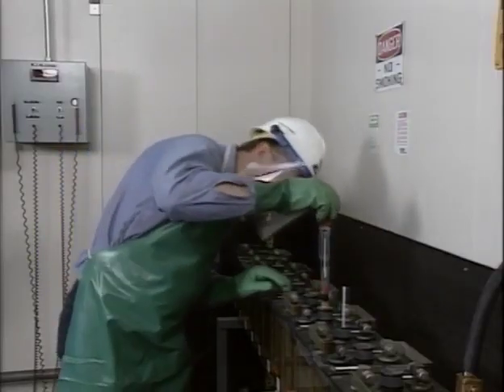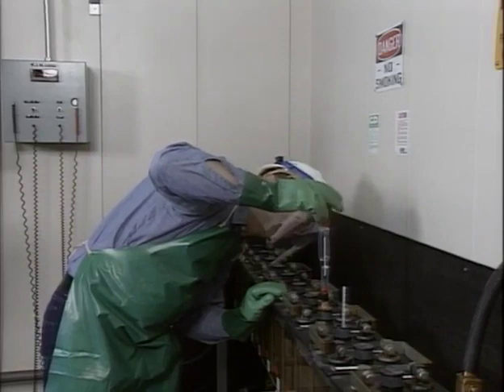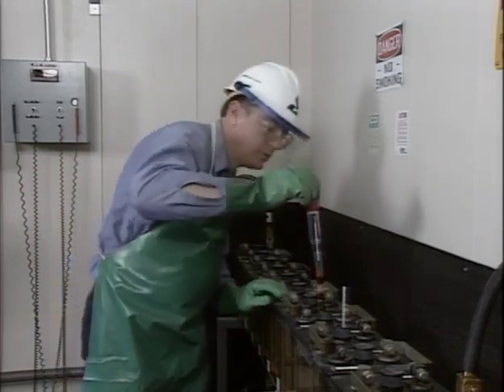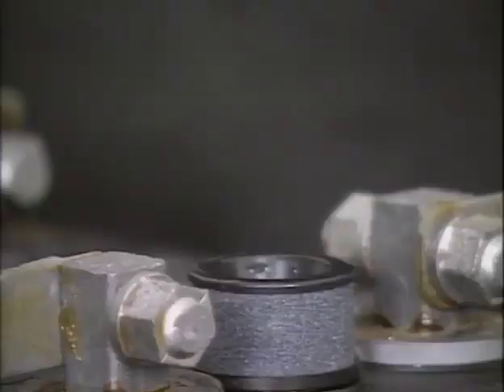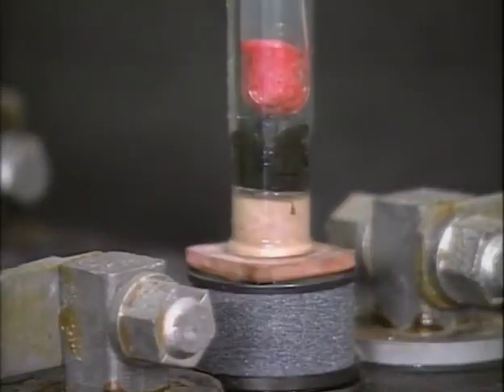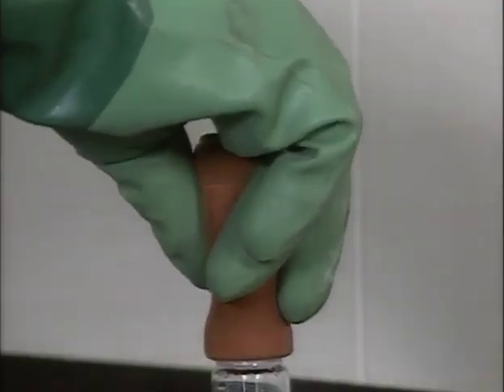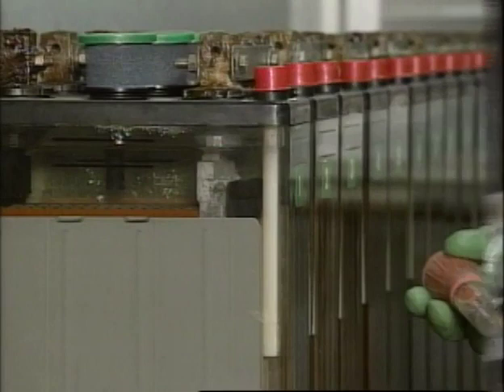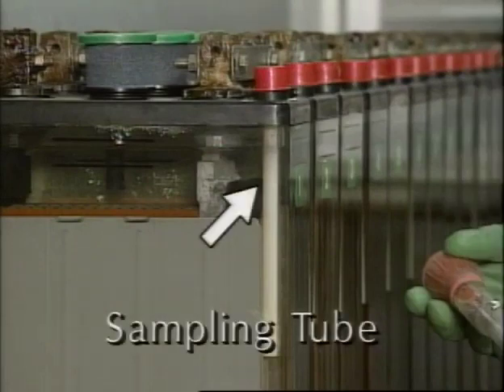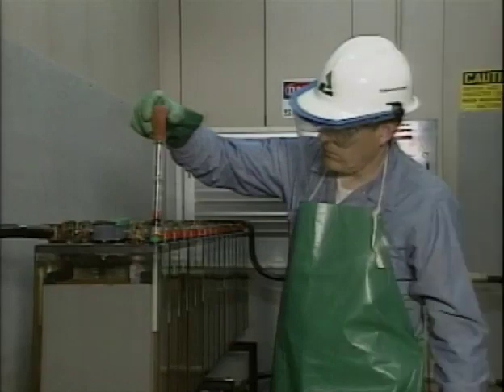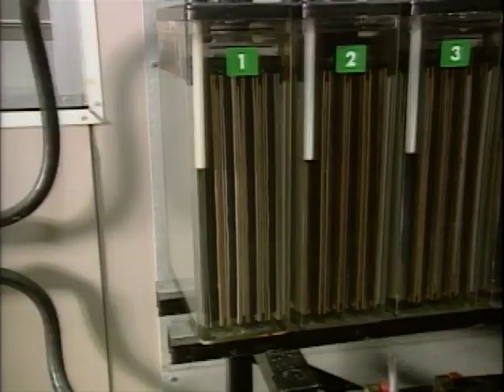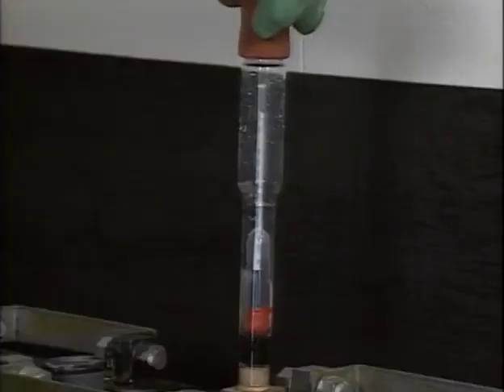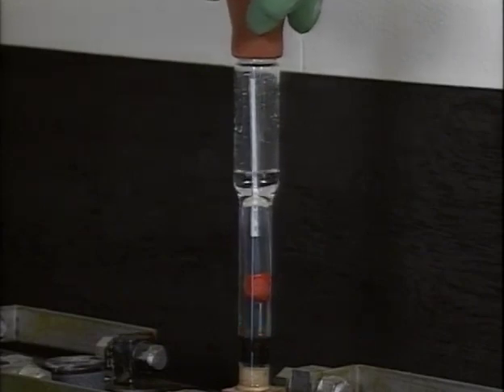When specific gravity is checked, all required safety equipment should be worn, and all required safe working practices should be followed to the letter. To measure cell-specific gravity, the syringe nozzle is inserted into the cell. The bulb is squeezed and released to draw a sample into the barrel. Some cells have a sampling tube. If electrolyte is taken from a sampling tube, the first sample is discharged into the vent well. Specific gravity isn't read from the first sample because the electrolyte in the sampling tube doesn't mix with and isn't representative of the rest of the electrolyte in the cell. A second sample is drawn for the specific gravity reading.